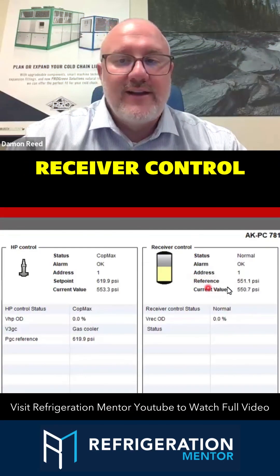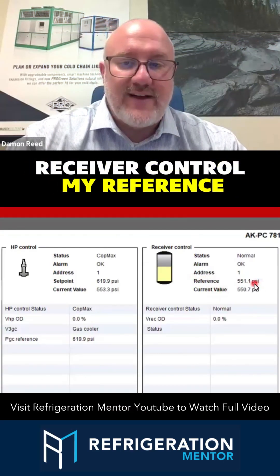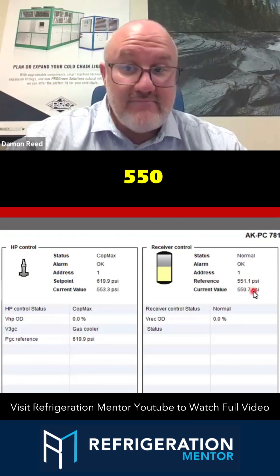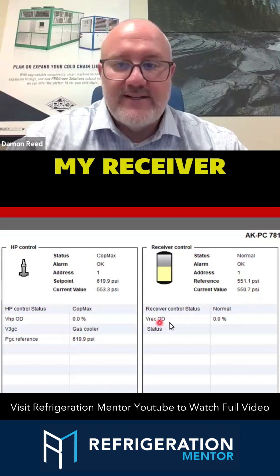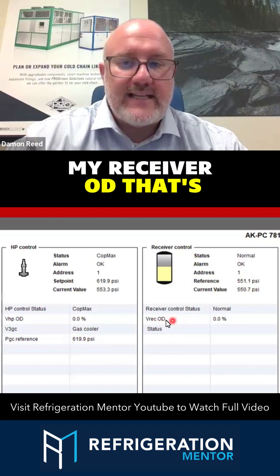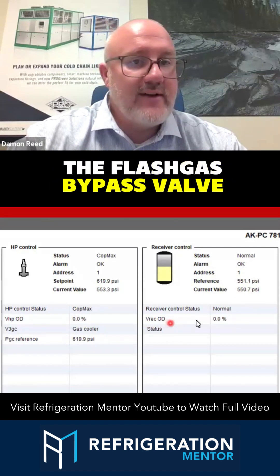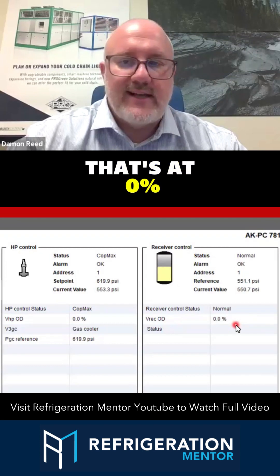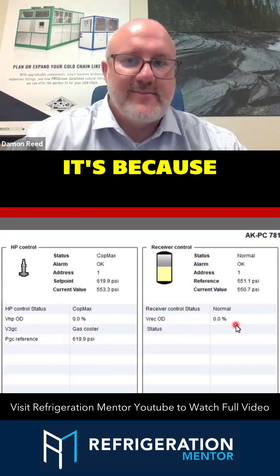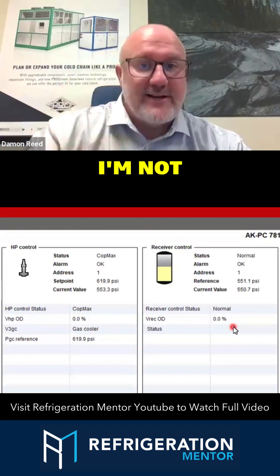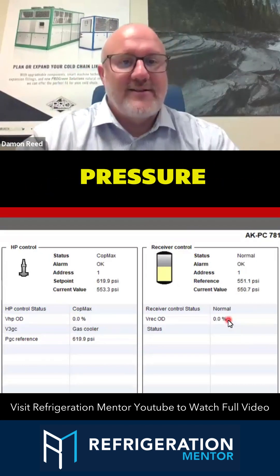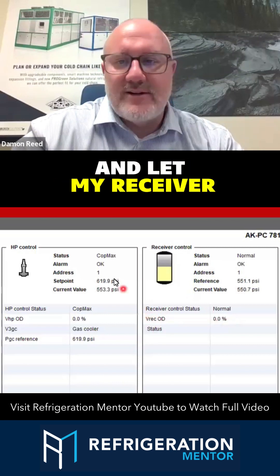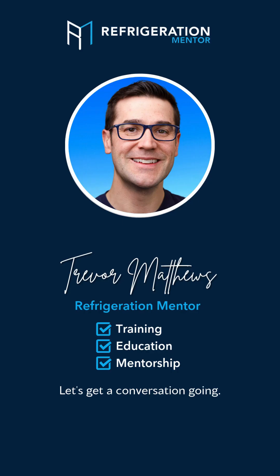Receiver control: my reference is 550 and my current value is 550. My receiver output — that's the flash gas bypass valve output — is at 0%. That's because my receiver is at set point. I'm not generating any excess pressure, so I'm not asking it to open up and let the receiver pressure come down.